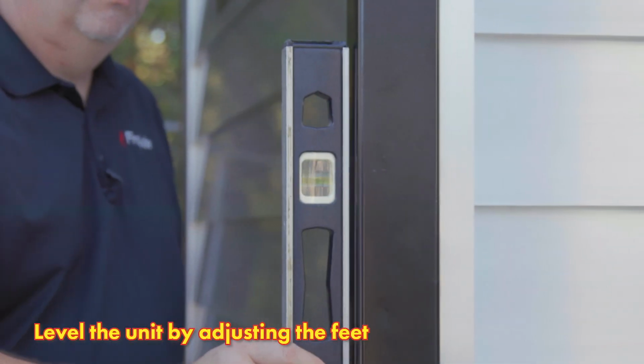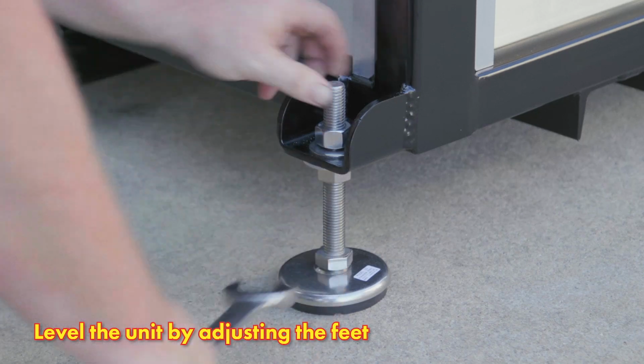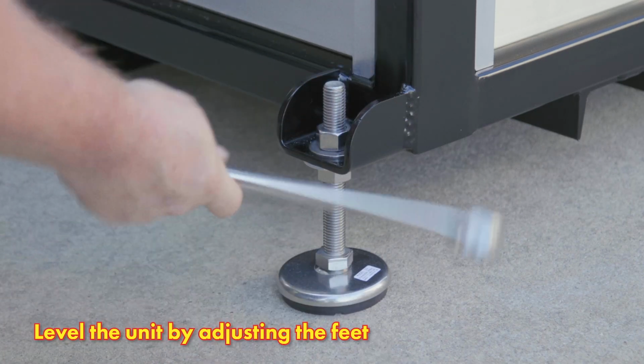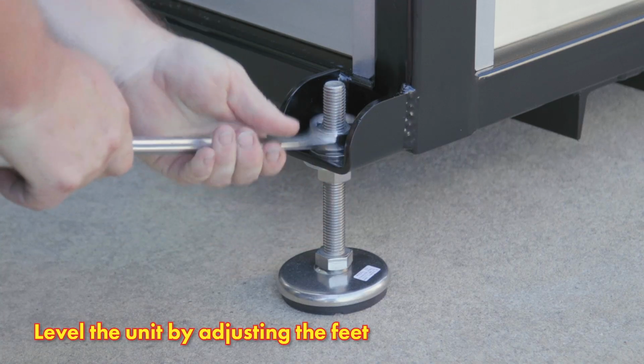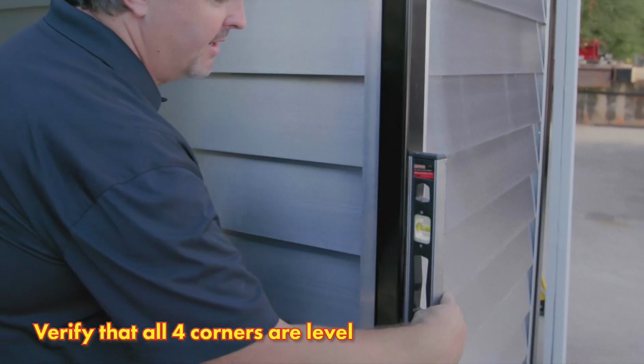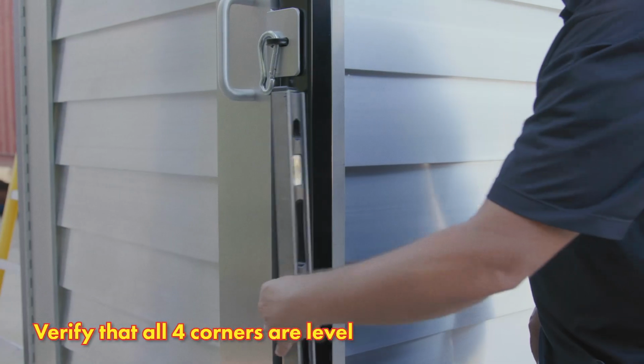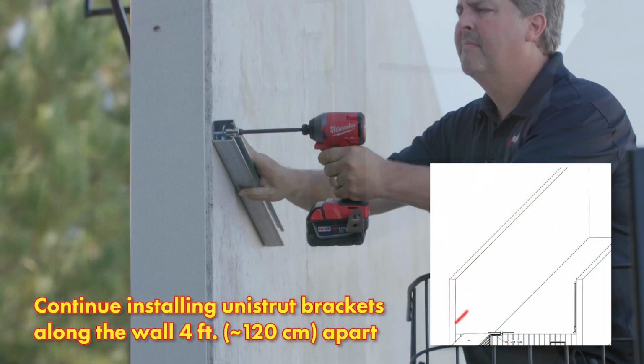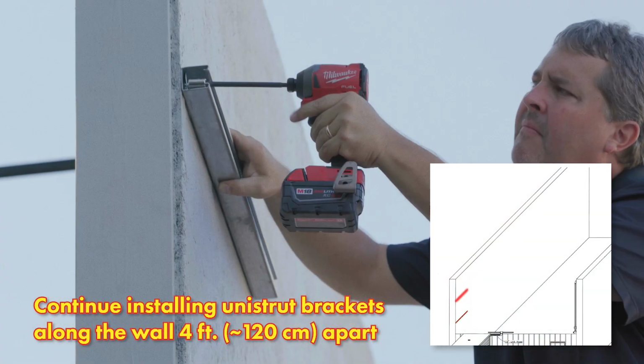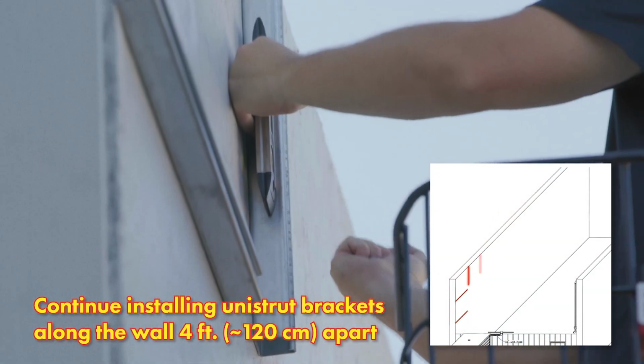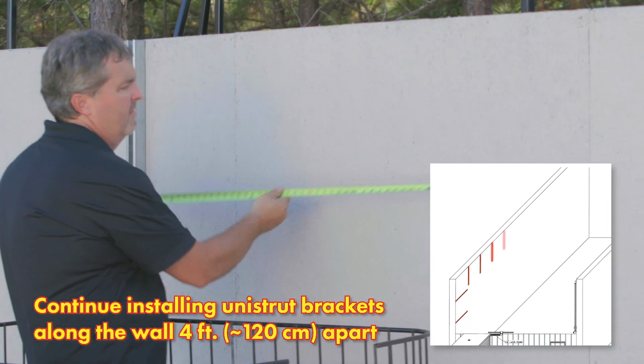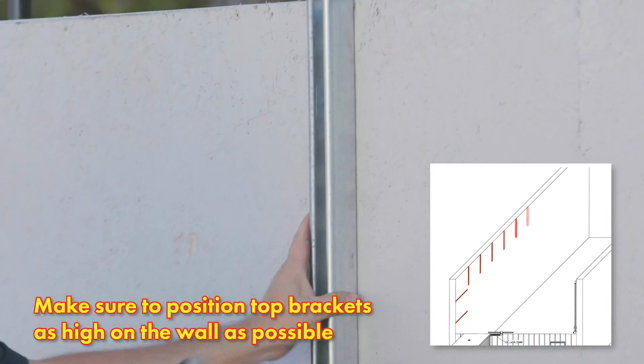Level the unit by adjusting the feet, using the bottom nut to adjust the height and the top nut to secure its position once in place. Verify that all 4 corners are leveled. Install the unistrut brackets along the wall to mount your piping. Position the brackets roughly 4 feet apart. Make sure to position the top brackets as high on the wall as possible.